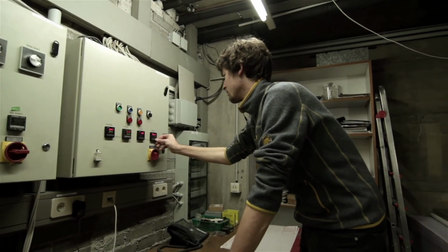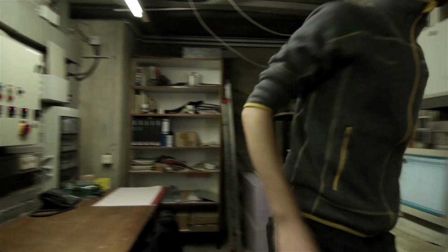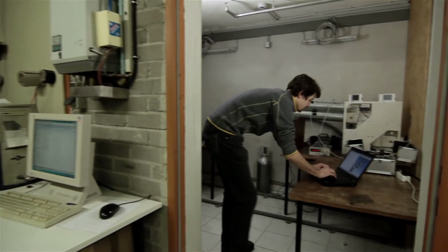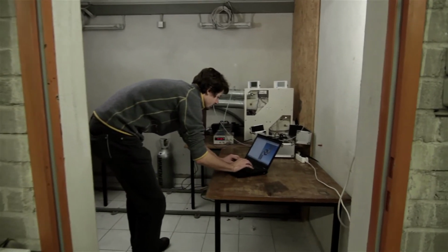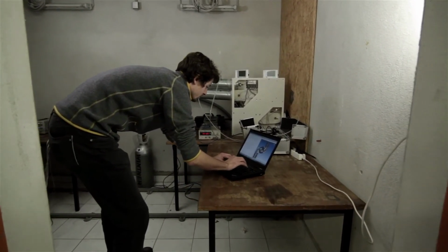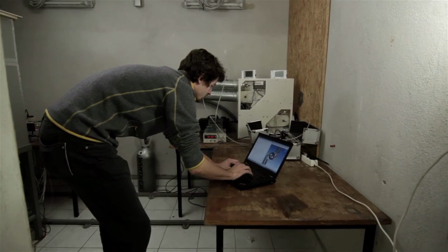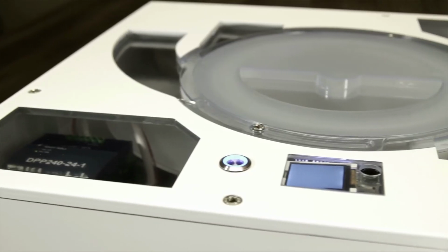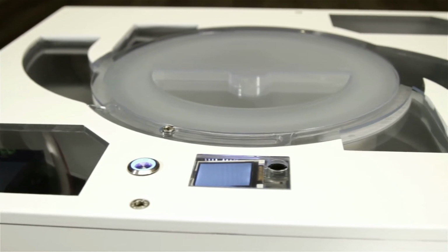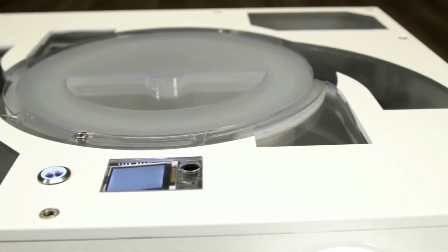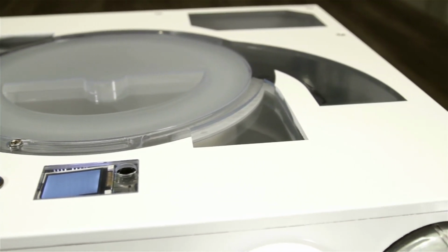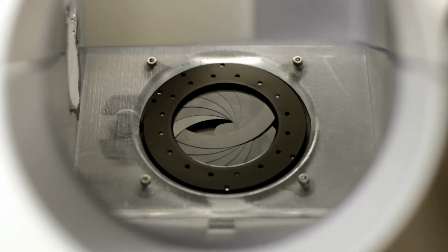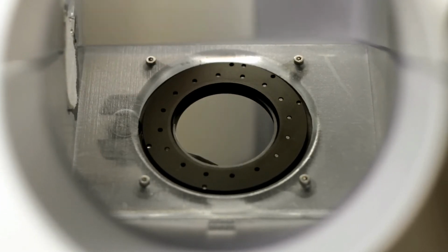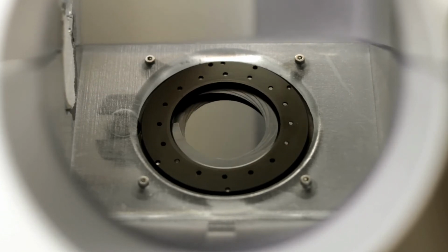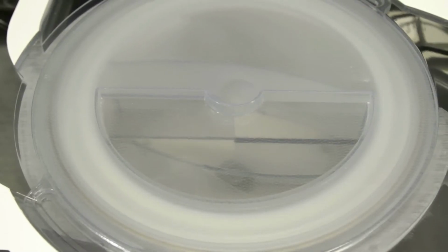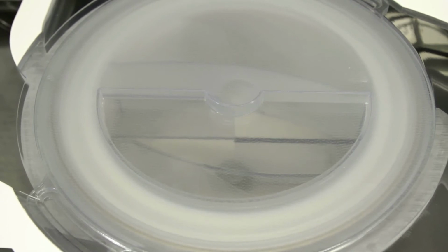The prototype was installed and tested in the climatic chamber, where different climatic and weather conditions can be simulated by changing the outdoor and indoor temperature and humidity parameters. With this prototype, we were not just able to develop a compact, decentralized ventilation system for the retrofit installation in the existing building stock, but we were also able to demonstrate that these kind of devices can have a high efficient heat recovery by making aerodynamical and thermodynamical changes to existing concepts.